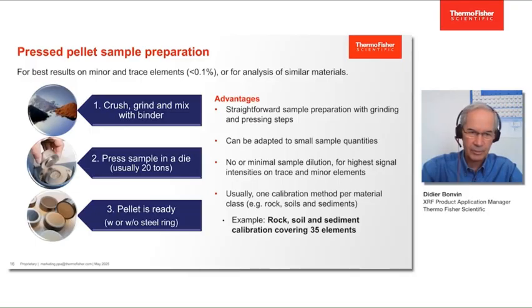Usually 20-ton pressure is sufficient. And finally, we get a nice pellet with a flat surface that is easy to present to the XRF spectrometer. So it's a very simple technique to prepare the sample, and that's one of the advantages. This straightforward sample preparation with grinding and pressing steps can also be adapted to small quantities if we don't have enough material. There is no or minimal sample dilution.